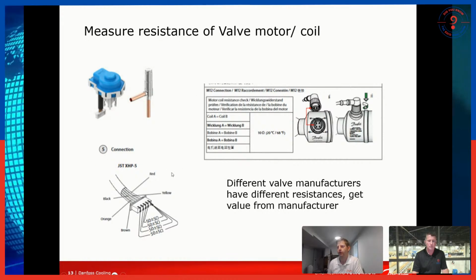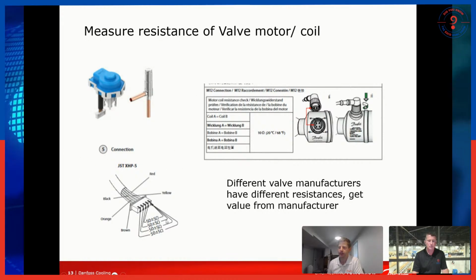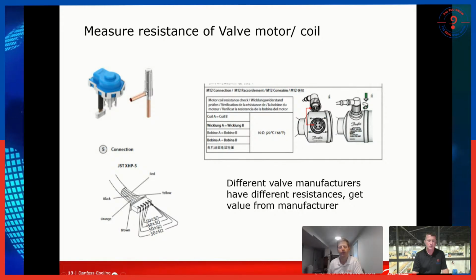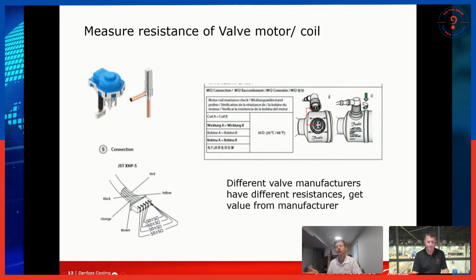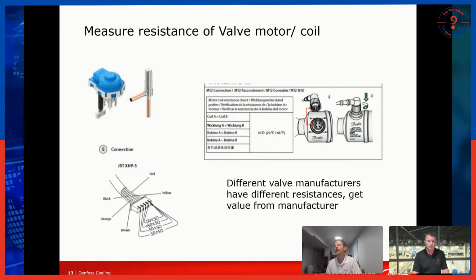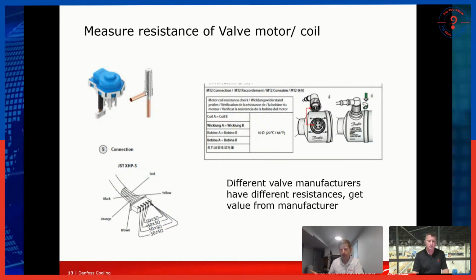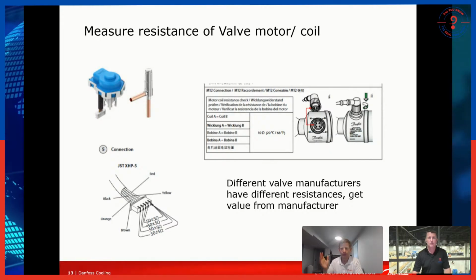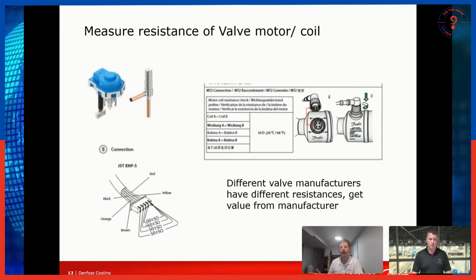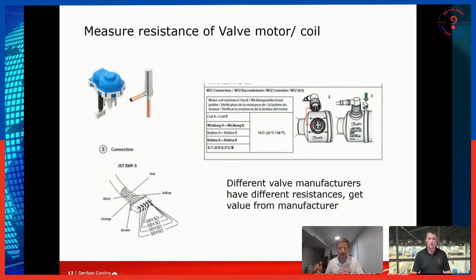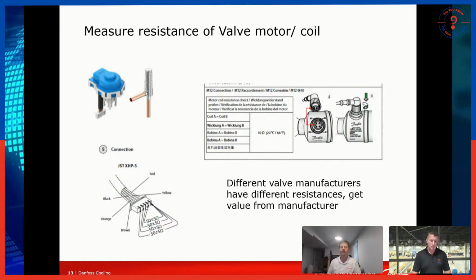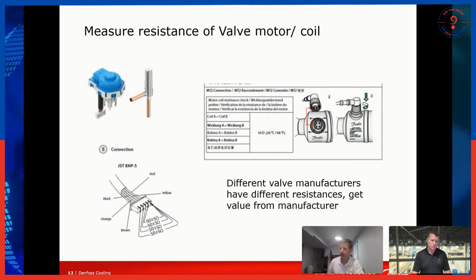Here's an example of one of our EXVs, an ETS6, and that one's supposed to ohm out at 50 ohms. You'd have to check with each individual manufacturer what it should be. But generally, it's a double-digit number. I've seen different values for different manufacturers. And if you find that this is way out of whack, or it's open, or it's closed, you've got continuity, that would give you a real indication that you've got a problem.